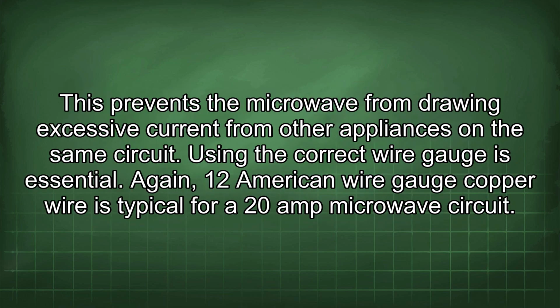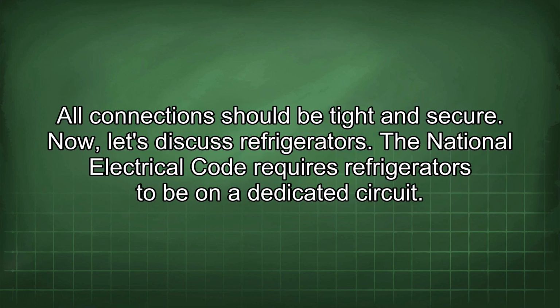This prevents the microwave from drawing excessive current from other appliances in the same circuit. Using the correct wire gauge is essential. Again, 12 American wire gauge copper wire is typical for a 20-amp microwave circuit. All connections should be tight and secure.